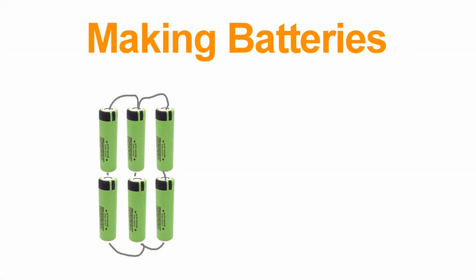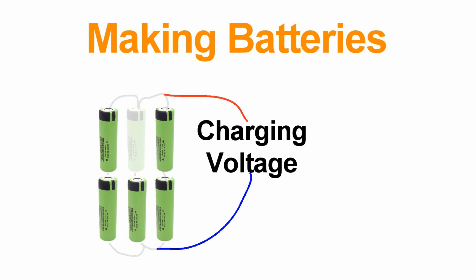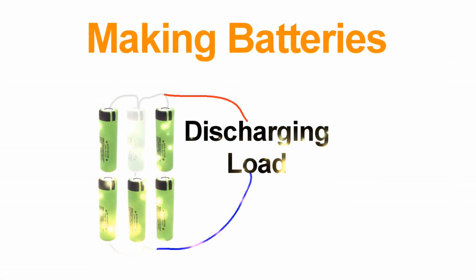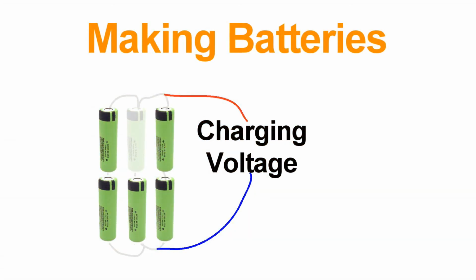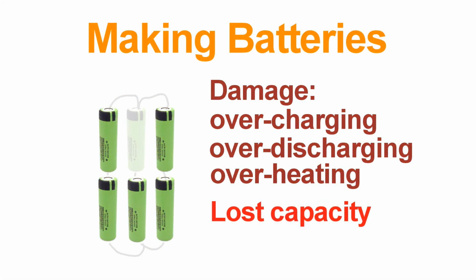There are some challenges in building performance systems with batteries like this. They arise mostly because it's not possible to make two cells which are the same. Here, for example, I've shown this cell as having slightly less capacity than the others. Each time the battery is charged, this rogue cell is overcharged and the one underneath it is undercharged. When the battery is under load, the rogue cell is over-discharged and the one underneath is under-discharged. This causes a progressive imbalance in the cells which leads to a combination of damage and underutilization of capacity.